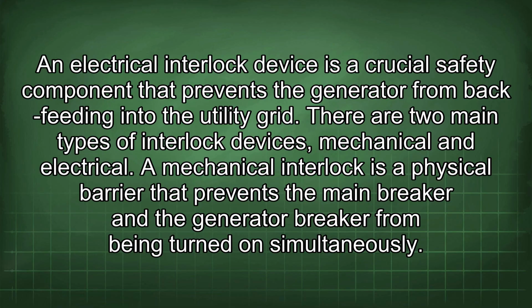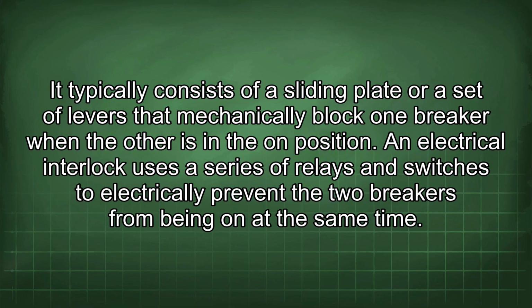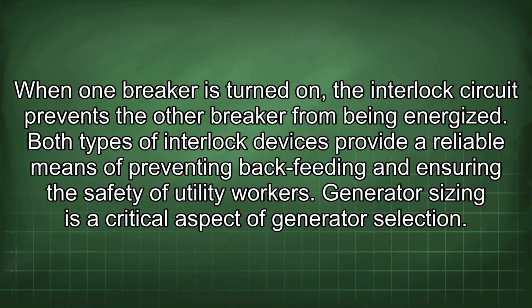A mechanical interlock is a physical barrier that prevents the main breaker and the generator breaker from being turned on simultaneously. It typically consists of a sliding plate or a set of levers that mechanically block one breaker when the other is in the on position. An electrical interlock uses a series of relays and switches to electrically prevent the two breakers from being on at the same time. When one breaker is turned on, the interlock circuit prevents the other breaker from being energized. Both types of interlock devices provide a reliable means of preventing backfeeding and ensuring the safety of utility workers.